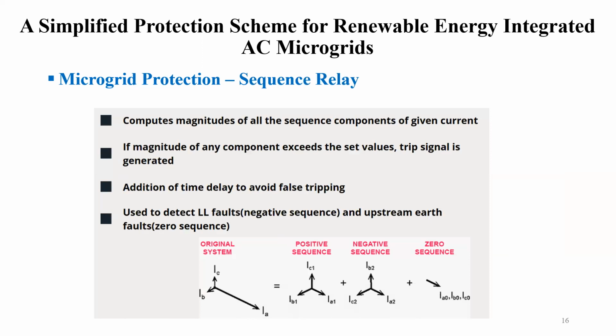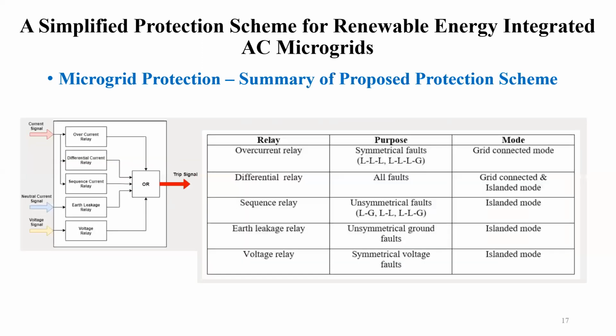Then we have the sequence relay. Again, it computes the magnitude of all sequence components of the given current. If the magnitude of a component exceeds the set value, the trip signal is generated. Addition of a time delay is used to avoid false tripping, and it is used to detect line-to-line faults for negative sequence and upstream earth fault for zero sequence currents. So this is the usage of the 5 relays which we have used in our proposed protection scheme.